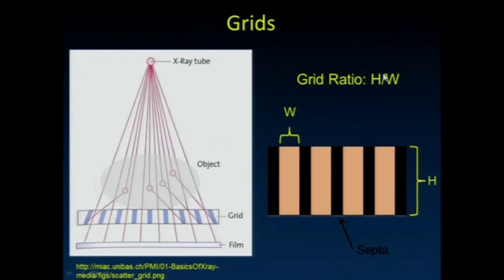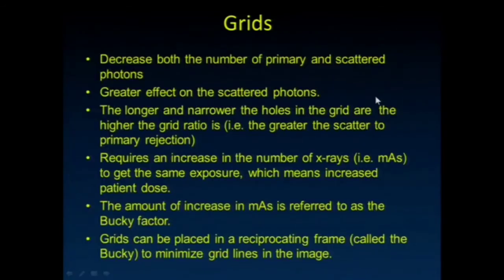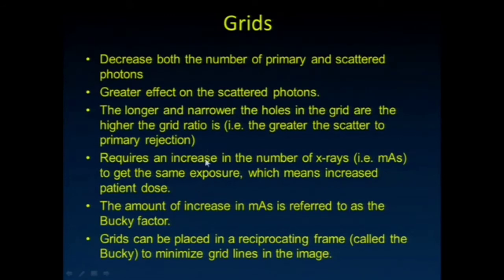The grid ratio is the height of the holes divided by the width of the holes. Grids decrease both primary and scatter transmission, but have a greater effect on scatter. The longer and narrower the holes, the more rejection they provide. Grids always require an increase in the number of x-rays because fewer x-rays reach the detector.